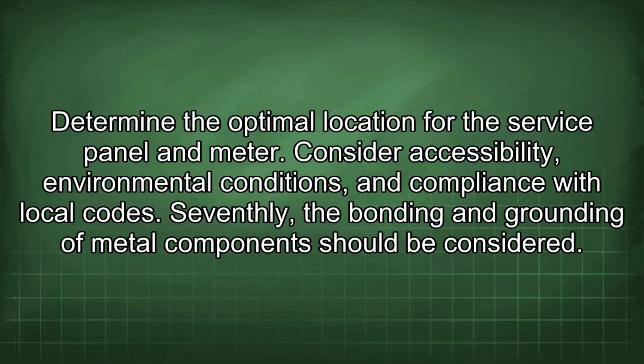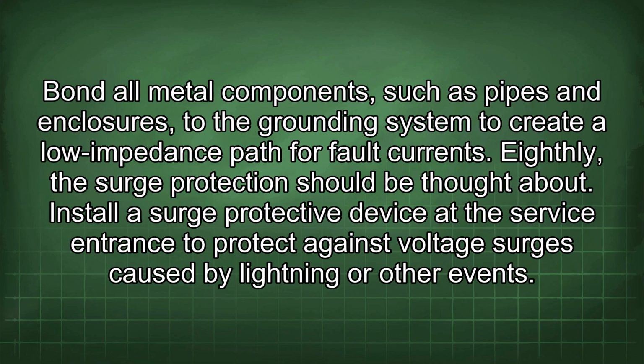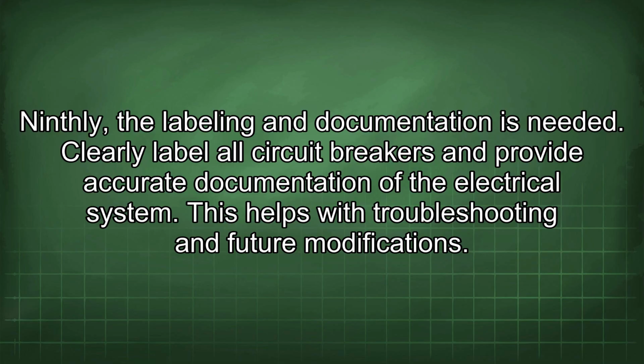Seventhly, the bonding and grounding of metal components should be considered. Bond all metal components, such as pipes and enclosures, to the grounding system to create a low impedance path for fault currents. Eighthly, surge protection should be thought about. Install a surge protective device at the service entrance to protect against voltage surges caused by lightning or other events. Ninthly, labeling and documentation are needed. Clearly label all circuit breakers and provide accurate documentation of the electrical system.